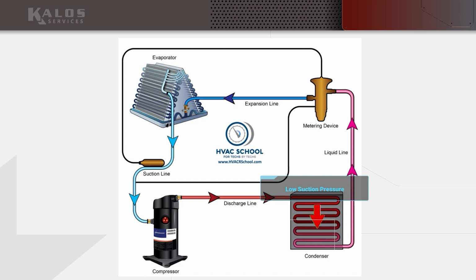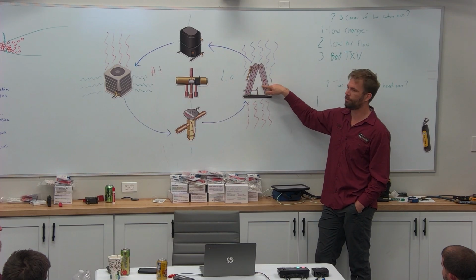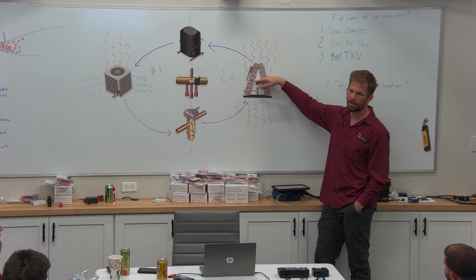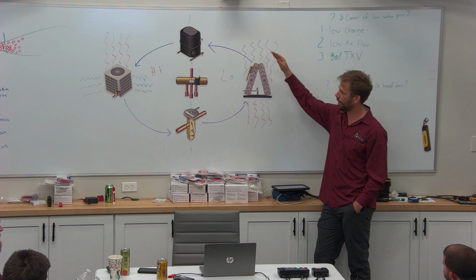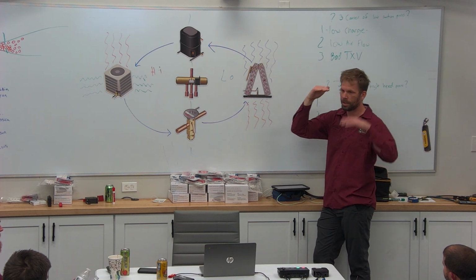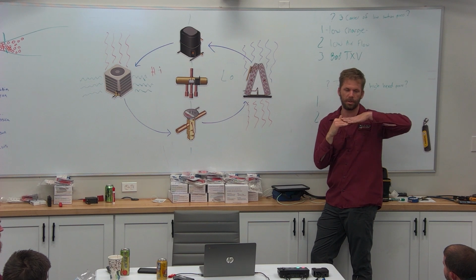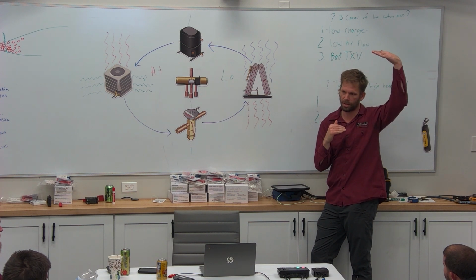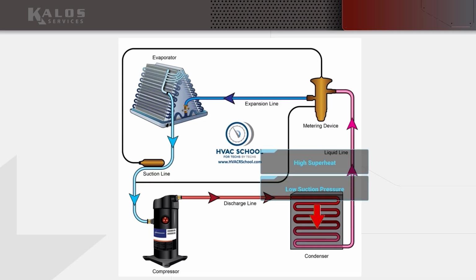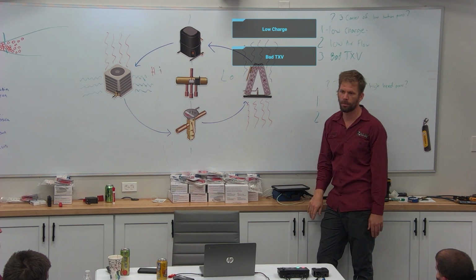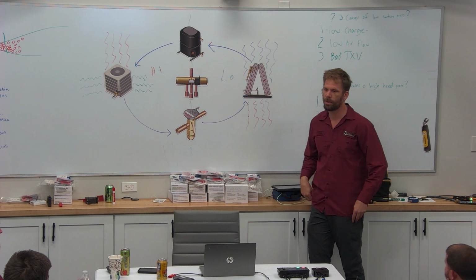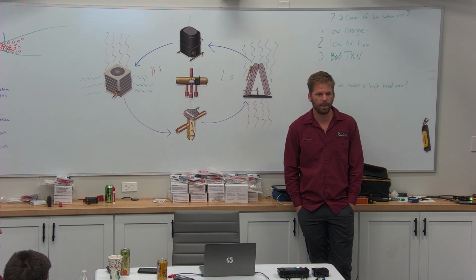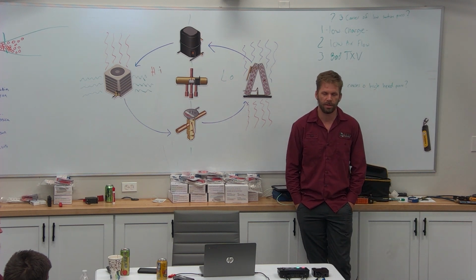Because we don't have very much liquid coming in, it's boiling off really fast and creating a really high superheat. So it has low suction pressure. We're also bringing our suction saturation down, so we're creating a bigger difference between saturation and the line temperature. So high superheat. Low suction, high superheat for 1 and 3. Both of them exactly the same.